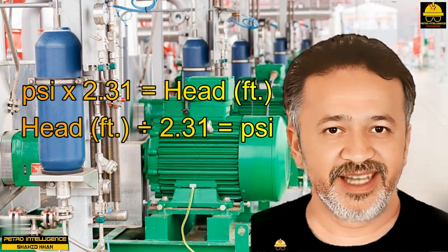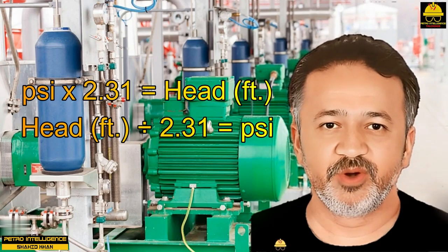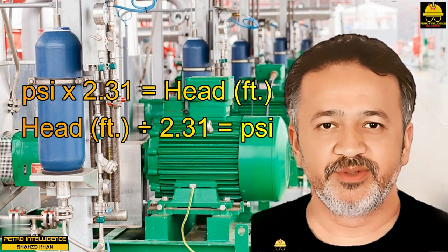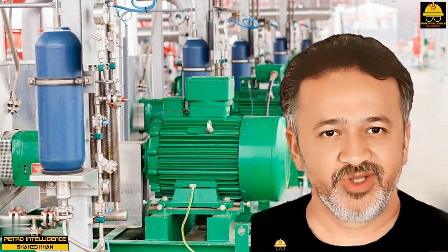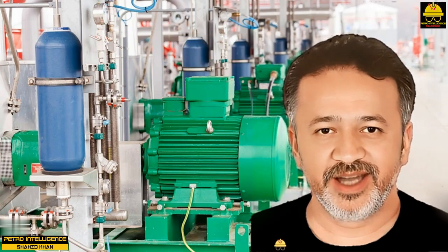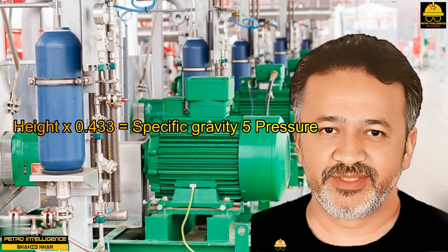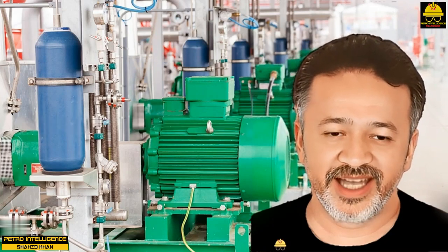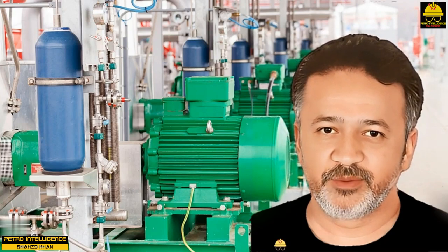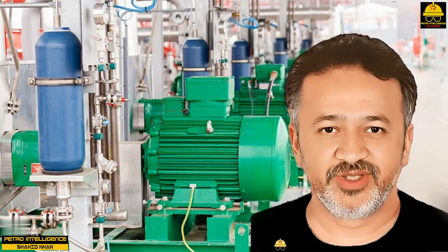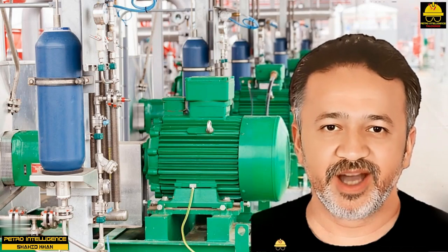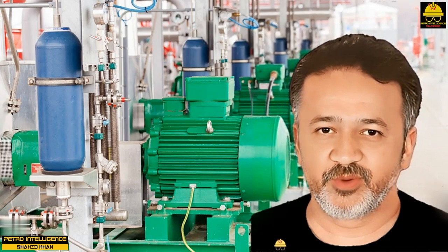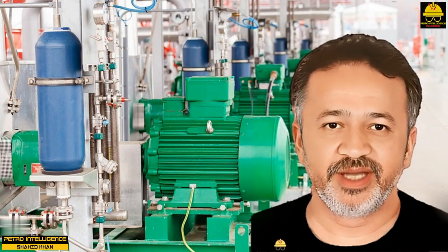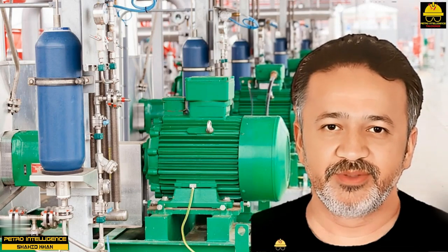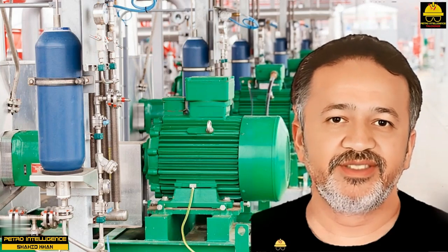Expressed another way, psi times 2.31 equals head, in feet, or head, in feet, divided by 2.31 equals psi. A common equation for determining pressure is height times 0.433 times specific gravity equals pressure. To calculate the required differential head, H, we need to know the specific gravity of propane. Specific gravity of propane equals 0.485. The unknown factor is delta P, differential pressure. To solve for delta P, we must pay close attention to the variables that contribute to pressure changes in a process system.